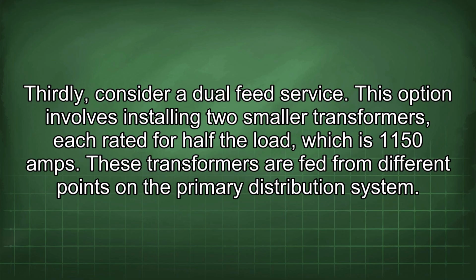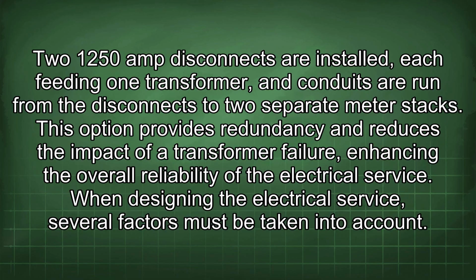This option involves installing 2 smaller transformers, each rated for half the load, which is 1150 amps. These transformers are fed from different points on the primary distribution system. 2 1250 amp disconnects are installed, each feeding 1 transformer, and conduits are run from the disconnects to 2 separate meter stacks. This option provides redundancy and reduces the impact of a transformer failure, enhancing the overall reliability of the electrical service. When designing the electrical service, several factors must be taken into account.